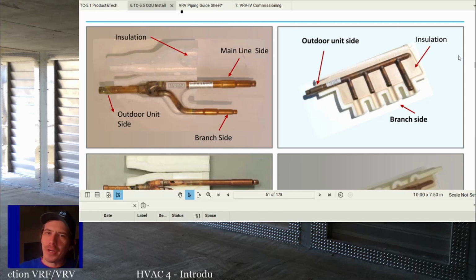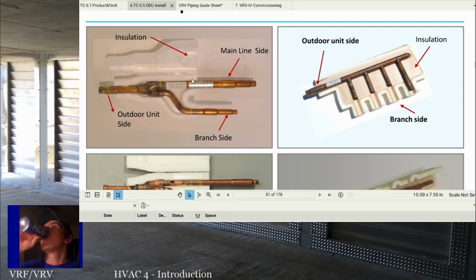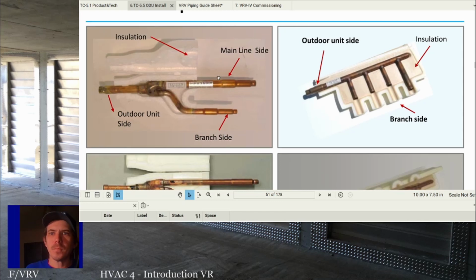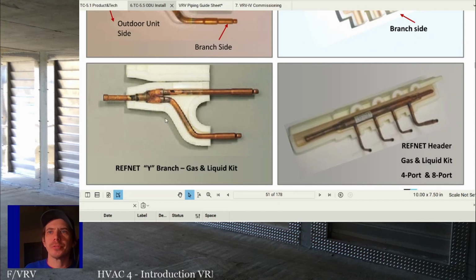But with VRF, you connect these Y kits by any means necessary, but make sure you have the right Y kit, because these are going to be bigger and smaller based on the size of the Y kit. So you can't use the wrong Y kit for the wrong tonnage. Okay. And because all this piping is based off the connected tonnage and how long the run is, you've got to have the proper kits and connections for that particular situation. But it doesn't matter. Just get A connected to B and you're good to go. So there's an outdoor unit, there's an indoor unit one.